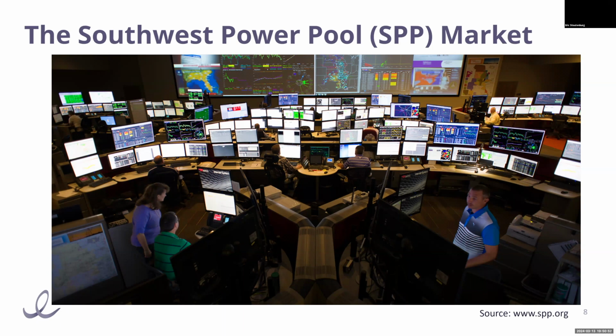Generally, it's easy to forecast until those threats come onto the grid, and it gets very difficult, as SPP experienced in the winter. So what batteries are really doing is providing these men and women operating the system a very responsive and dispatchable resource. Now, granted, it's only for short durations, but recovering from a tornado knocking out a large transmission line, or a coal plant tripping off, those issues are usually managed within about 5 minutes.